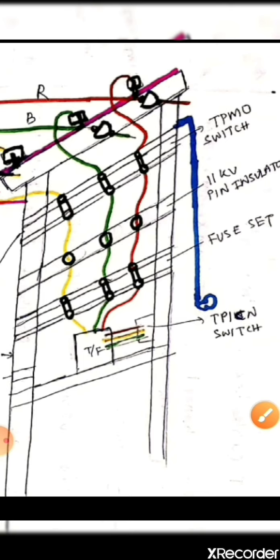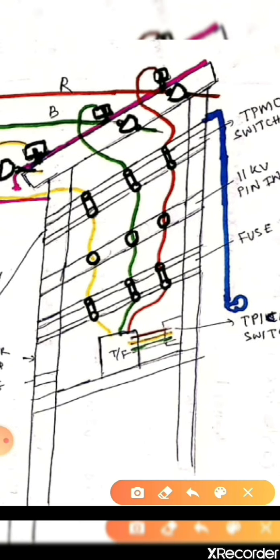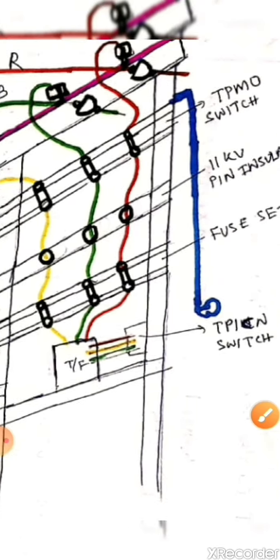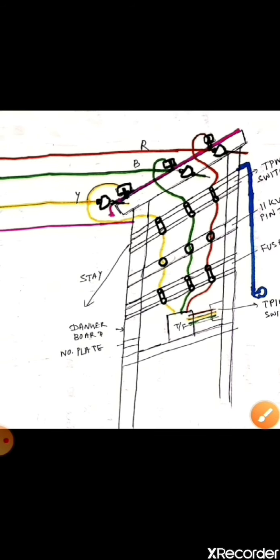Here it is an 11 by 0.4 kV transformer. So there are 3 incoming lines, but there are 4 outgoing lines: R, Y, B and neutral, and the 4 outgoing lines are connected to the TP ICN switch. And here the earthing will be done.